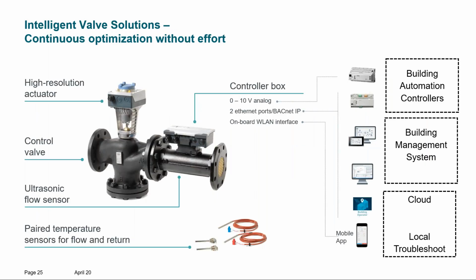Now, I would like to show you what an intelligent solution would look like and where it is different from a mechanical PICV. An intelligent solution doesn't just know the maximum flow set point and control the flow dynamically, but it has more elements. Thanks to a precise ultrasonic flow meter, it knows at any time during operation which flow goes into this riser, into this air handling unit.